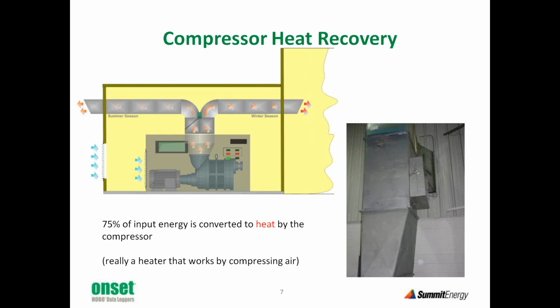So if we have a situation where there is negative pressure in the building, and in the winter we're tending to suck cold air in through open dock doors and windows, in places where we don't want that cold air coming in, it impinges on workers, and then we end up installing heaters nearby. You can avoid that situation by pressurizing the building. So a heat recovery system like this has several benefits.